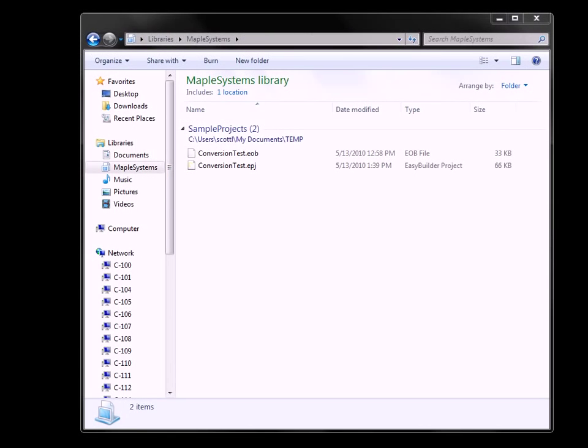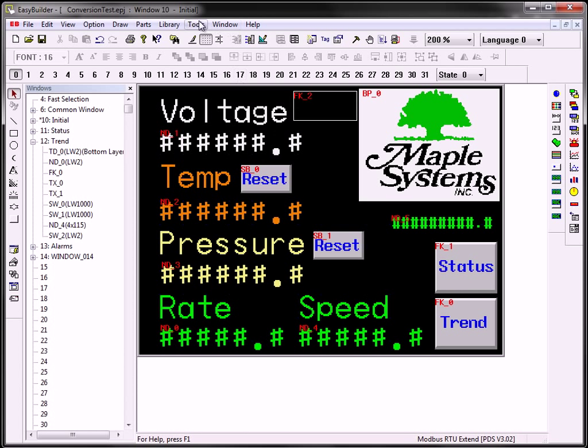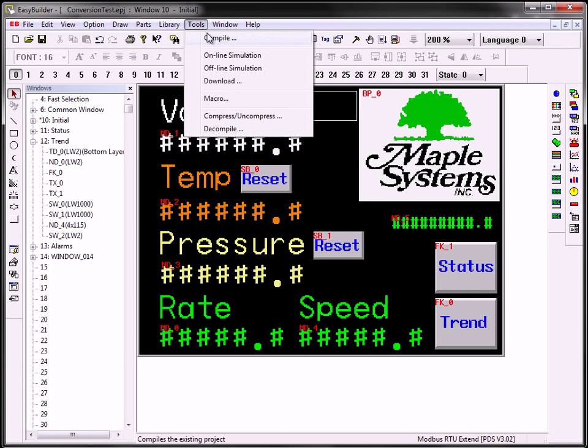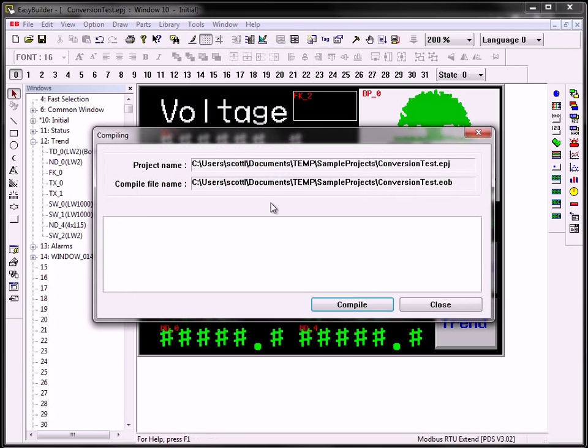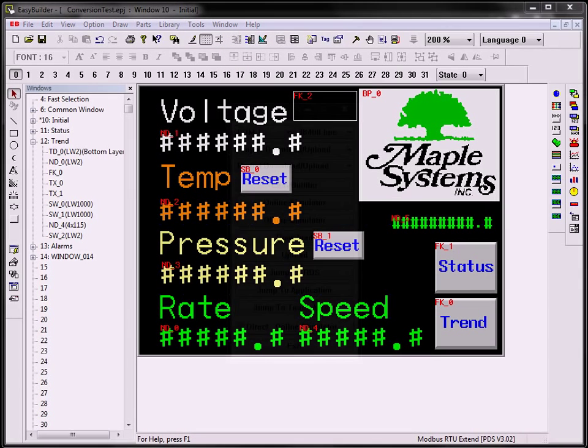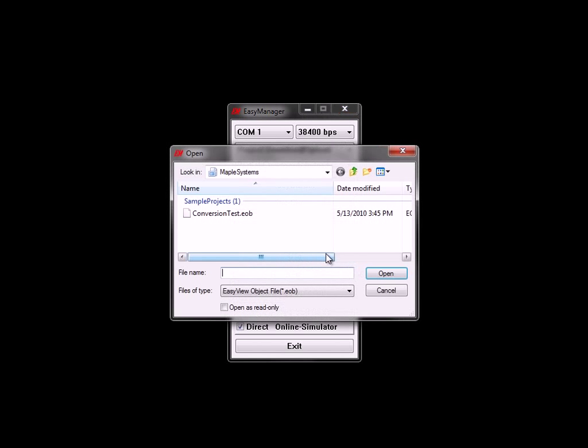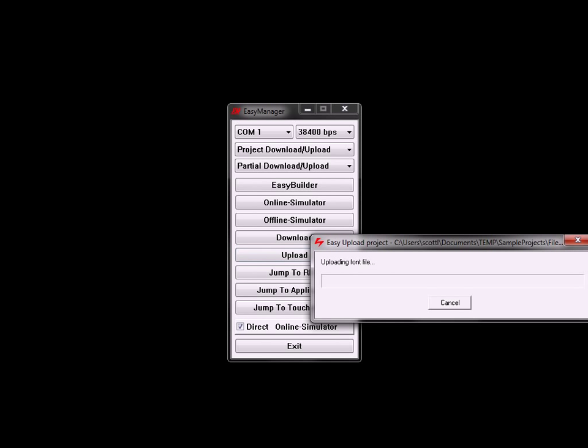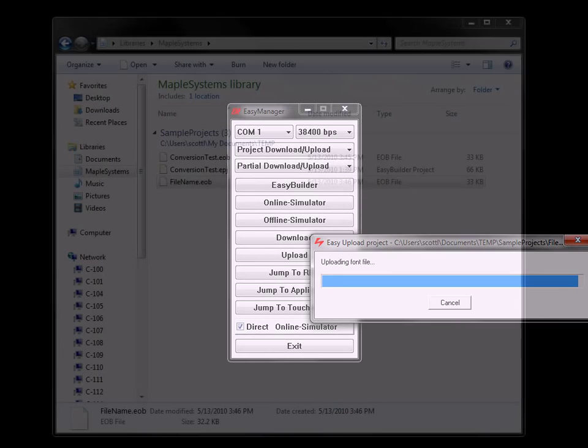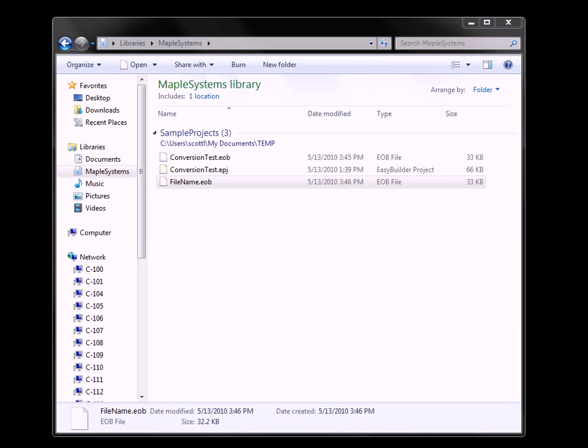If you're unable to locate your EOB file on your computer, open your project file in EasyBuilder, save your project and select Tools, Compile. To upload your project from an existing HMI, connect the configuration cable to the HMI and the PC, open EasyManager and click Upload. Enter a file name and select Open. The EOB file which was extracted from the HMI will later be used to convert the project into EasyBuilder 5000.